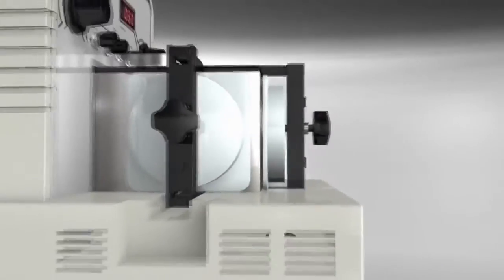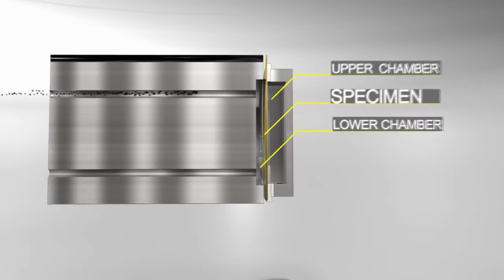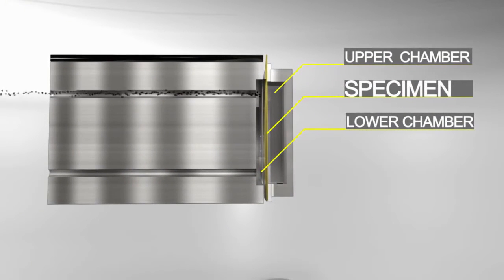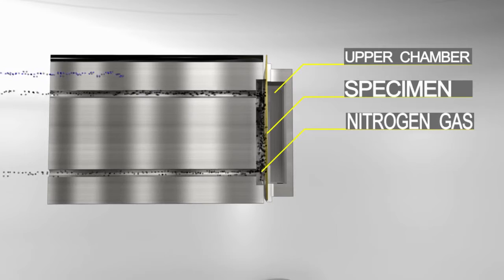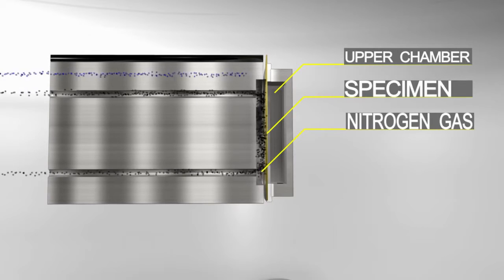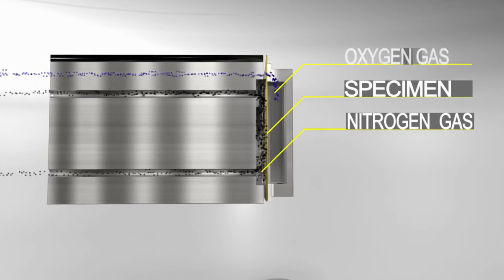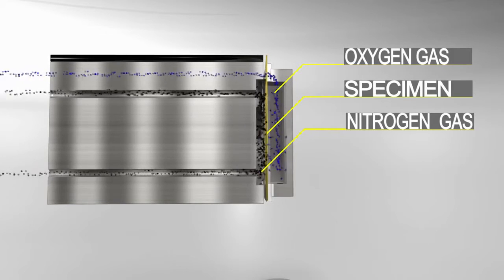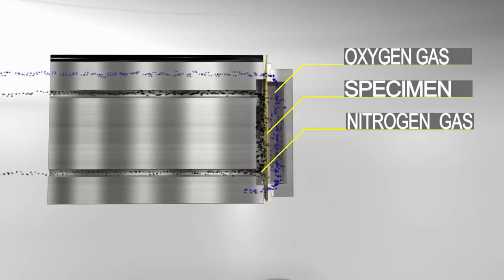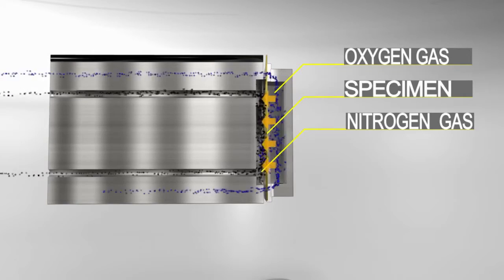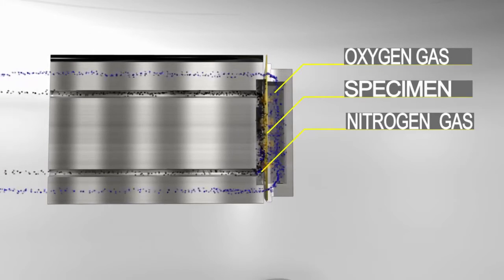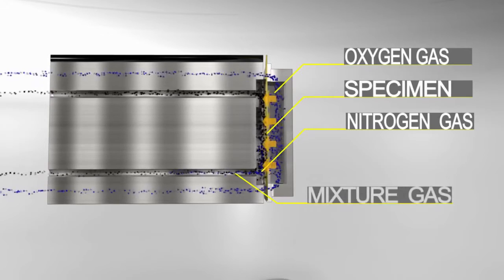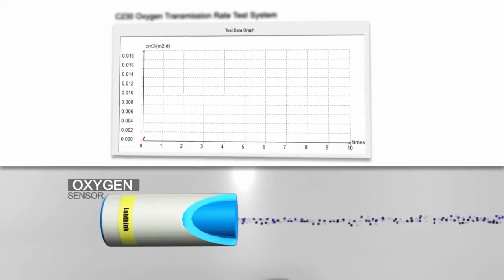C230 performs tests according to the following principle: The preconditioned specimen is mounted between the upper and lower chambers at ambient atmospheric pressure. One chamber contains oxygen or air; the other chamber is slowly purged by a stream of nitrogen. Due to the concentration difference, oxygen molecules permeate through the specimen into the nitrogen side and are taken to the coulometric sensor where proportional electrical signals are generated. The oxygen transmission rate is then obtained by analyzing and calculating the signals.